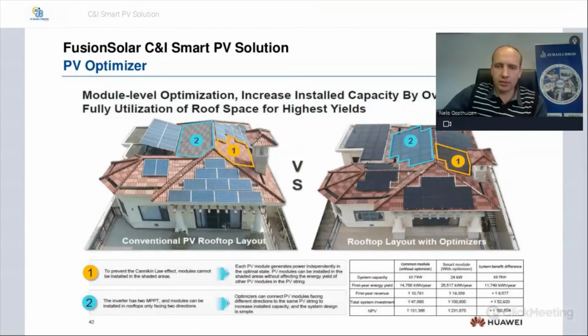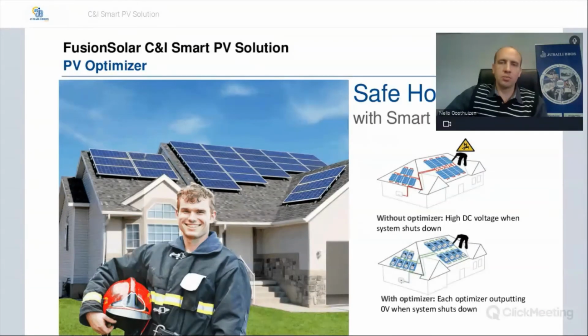If we look at the graphs here, you can see that a common module without optimizer can only do 13.7 kilowatt. But if you do a smart module with optimizers, you can do 24 kilowatt. That gives you 10.7 kilowatts more that you can add to the roof. So PV optimizers are definitely recommended if you've got complex roof systems and you would like to use the majority of the roof space that's available. Then PV optimizers ensure that you've got a safe house. Without optimizers, there is high DC voltage when the system shuts down, but with optimizers, each optimizer output is 0 when the system shuts down.